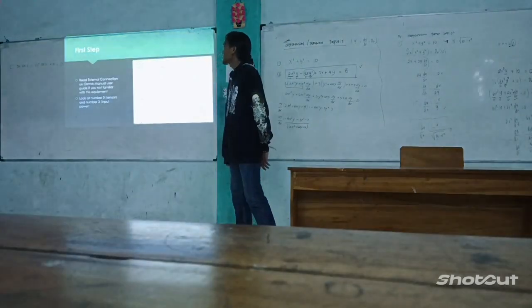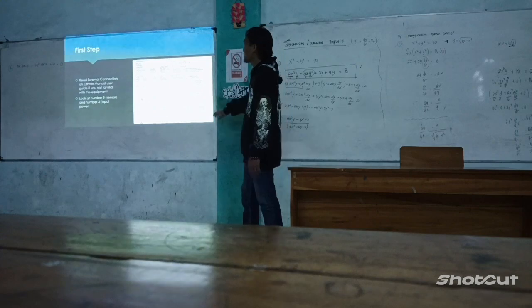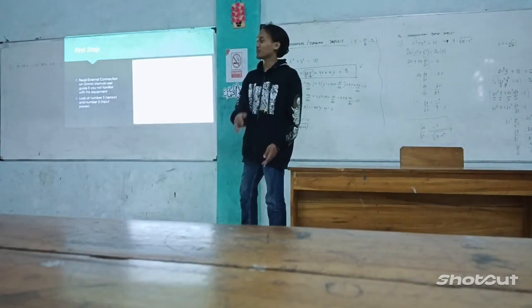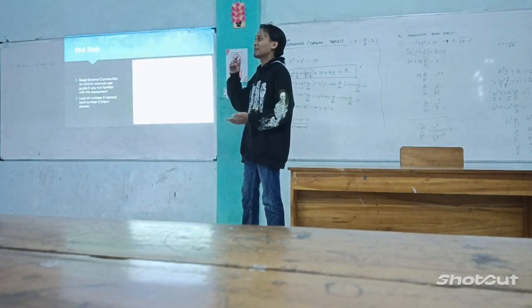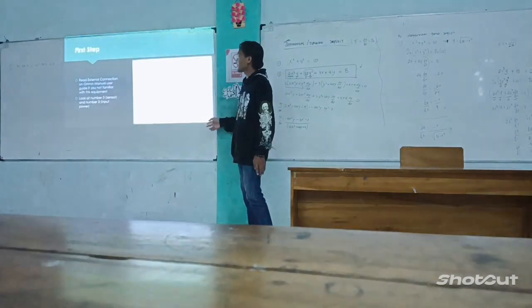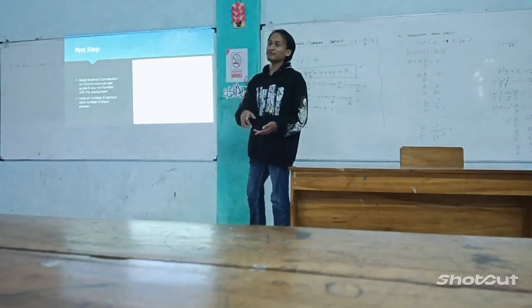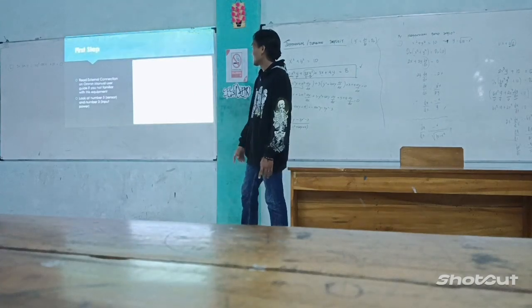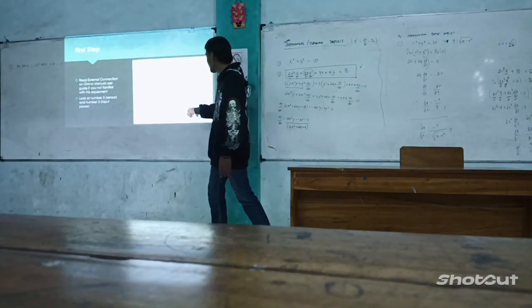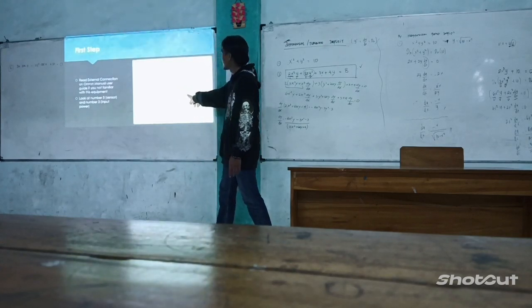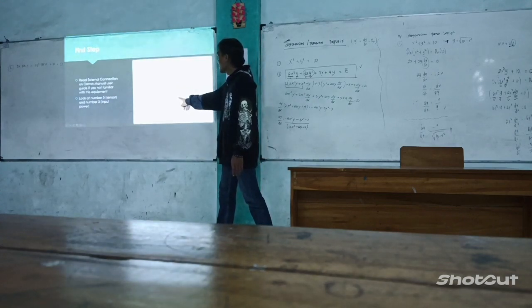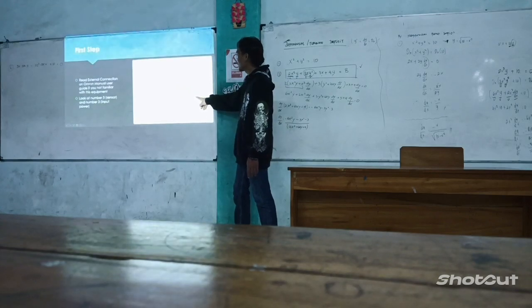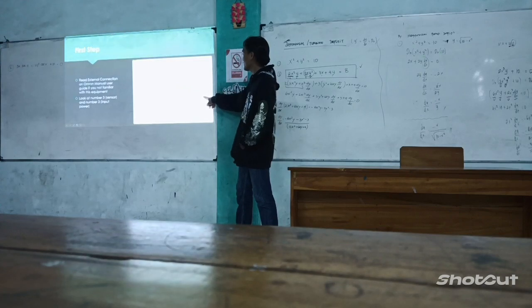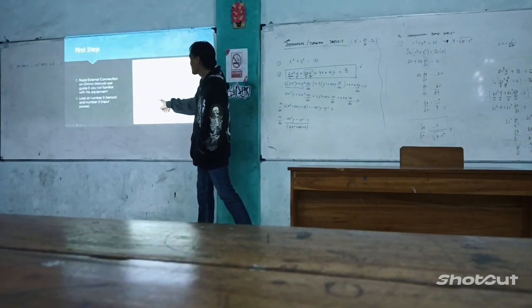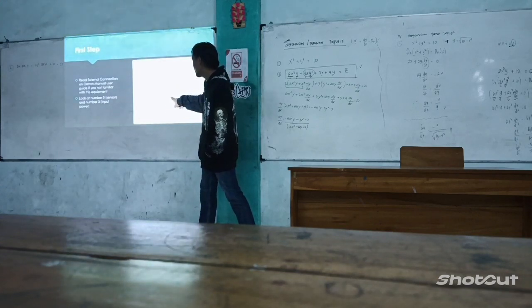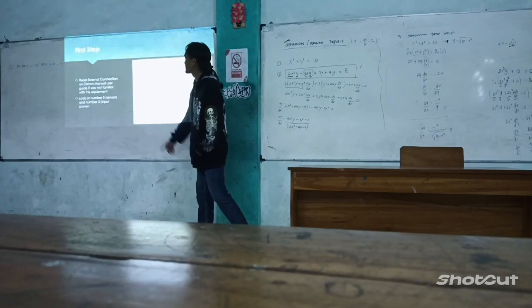First step, read the external connection in the Omron user manual. If you're not familiar with this equipment, the Omron user manual comes when you buy the equipment. But if you just want to learn or look at the manual, you can find it on Google. Number 3 is the input power supply. Numbers 11 and 12 take 100 to 240 volt AC, or in the DC model 24 VDC. And for the sensor, we use this PT at sockets number 4, 5, and 6. Next.